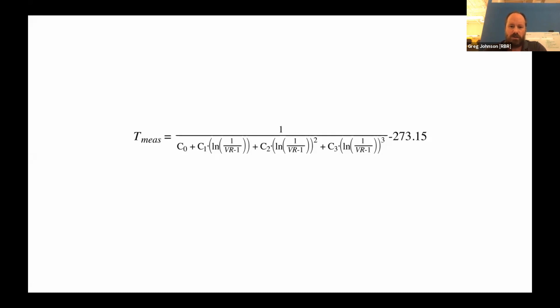And so we have the voltage ratio, or 1 over the resistance, the voltage ratio, natural logarithm in there, and then it's the reciprocal of the cube. And so what we're trying to do is to exercise the thermistor under a variety of conditions, as I said earlier, from -5 to 35. We usually do about 6-degree steps, so that makes it 8 steps, 9 steps over that temperature range. And then we do a least squares fit to obtain coefficients for the C0, C1, C2, C3 that you see there. The 273.15 is just the correction from Kelvin to Celsius, as you no doubt figured out.